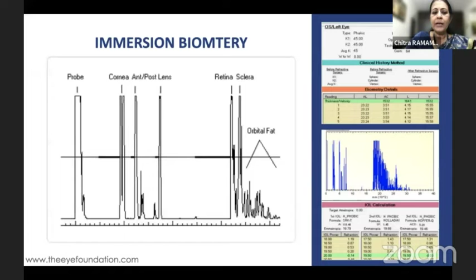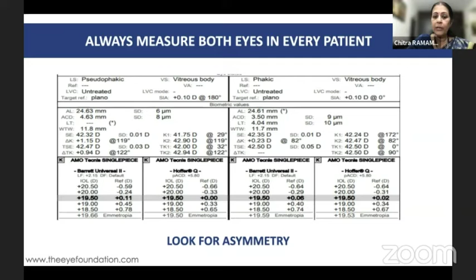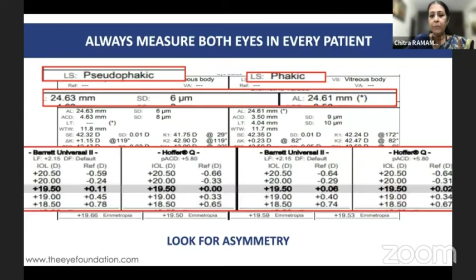You should also ensure that you have the scleral spikes, which ensure that the probe is well centered on the eye. You should take a number of readings. You should not compress the eyeball, and your standard deviation should be less than 0.06. When you're measuring two eyes, when you're doing a surgery in one eye, it's important that you look at the other eye, even if it's a pseudophakic eye, because if there is a gross difference in axial length, it should warn you that there's an asymmetry. Could it be an amblyopia which is being looked into or not looked into? All of these factors should be kept in mind.